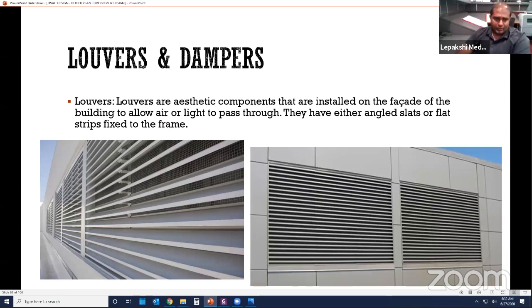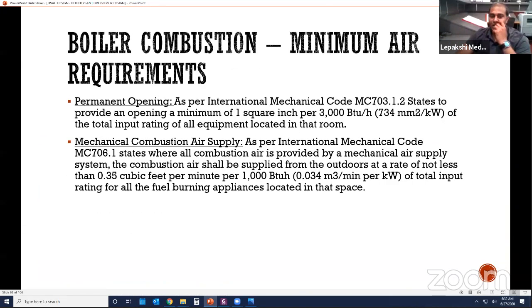So now you have the louver. At the same time, you can't have huge louvers, right? Sometimes you won't have enough space. What if the calculations tell you that you have to put a 20 feet wide by 20 feet high louver? That's not feasible. At that time, what you normally do is mechanically supply the air, which means you put a small fan over there.